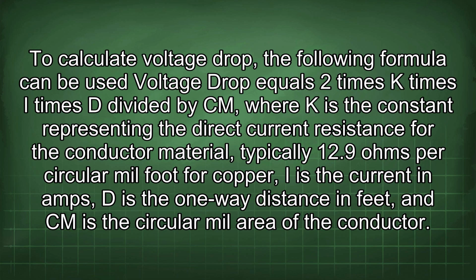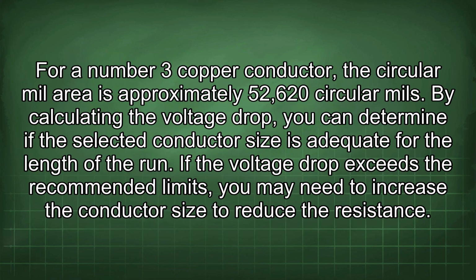I is the current in amps, D is the one-way distance in feet, and Cm is the circular mil area of the conductor. For number 3 copper conductor, the circular mil area is approximately 52,620 circular mils. By calculating the voltage drop, you can determine if the selected conductor size is adequate for the length of the run. If the voltage drop exceeds the recommended limits, you may need to increase the conductor size to reduce the resistance.